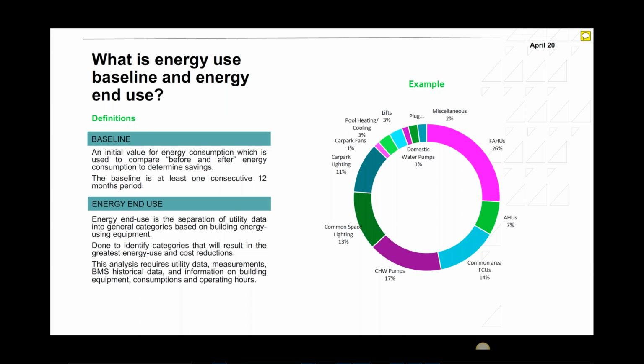So I would collect all the data from all the meters — what is the energy consumption — and that would be the total energy consumption. Normally I'd put it month-to-month on a spreadsheet. I might also correlate it to cooling degree days or average temperature to see if consumption is weather dependent. If this audit is for an industrial facility producing something, I'd want to look at energy consumption per production and also per weather, to see which variable the consumption depends on. So it could be an equation that covers both.